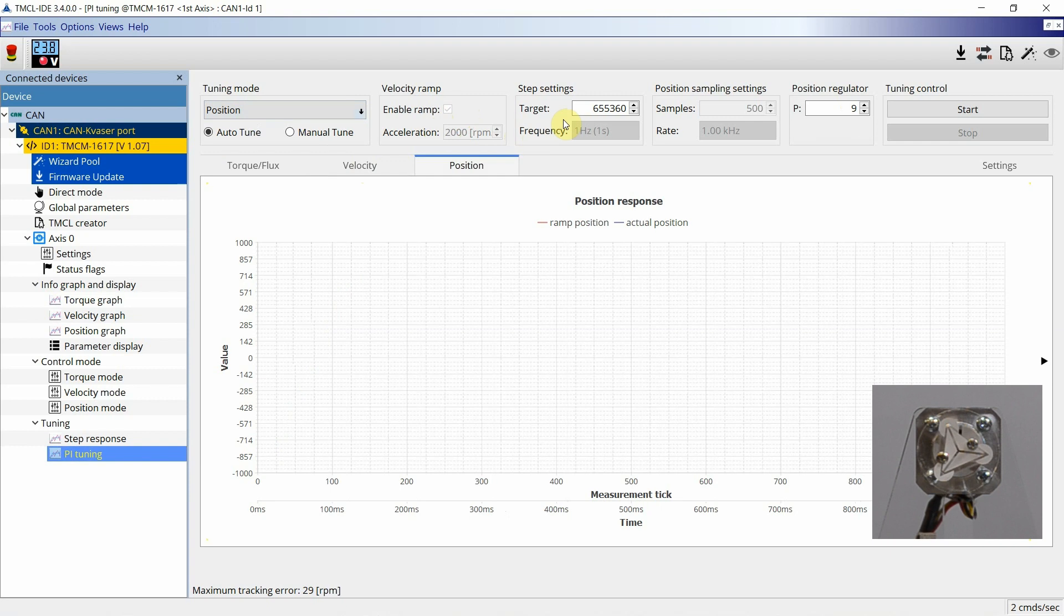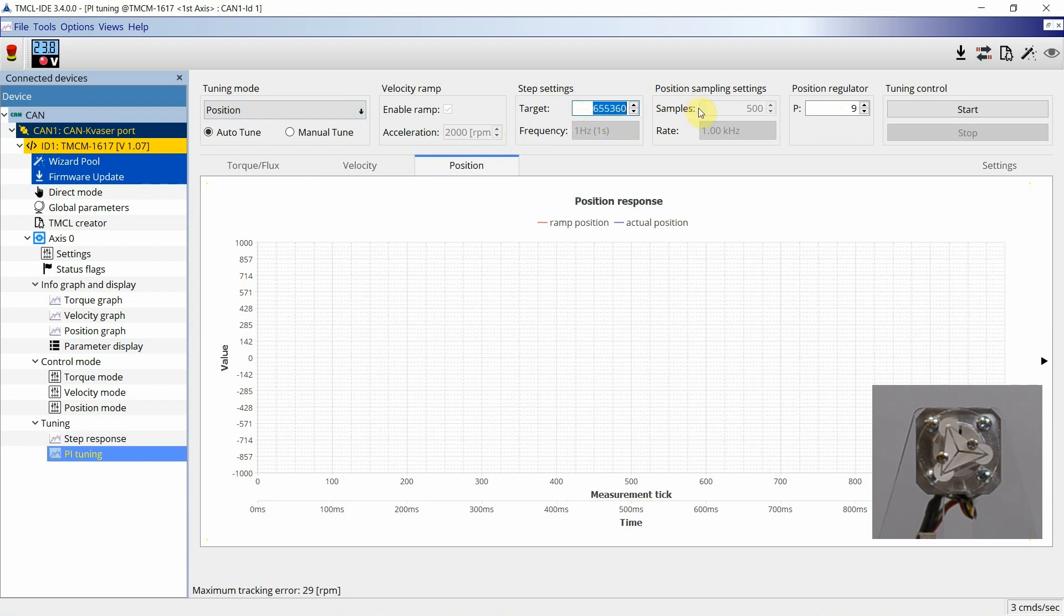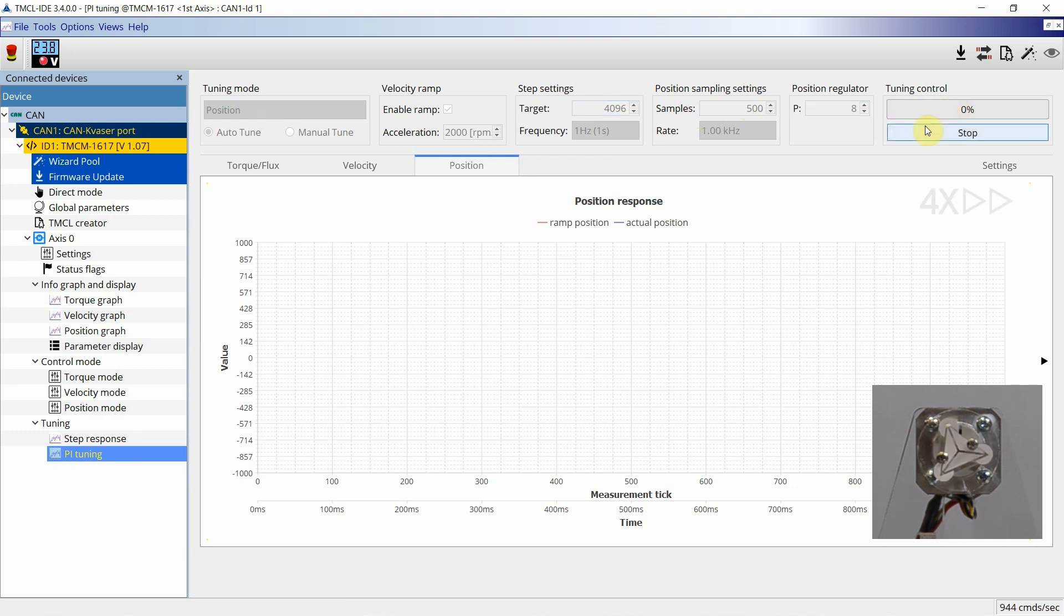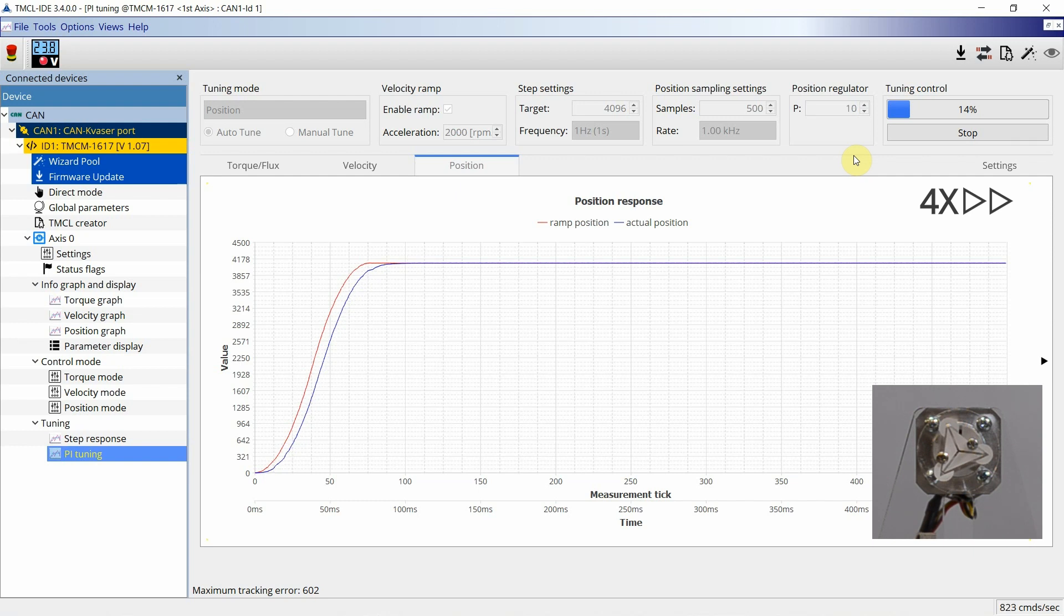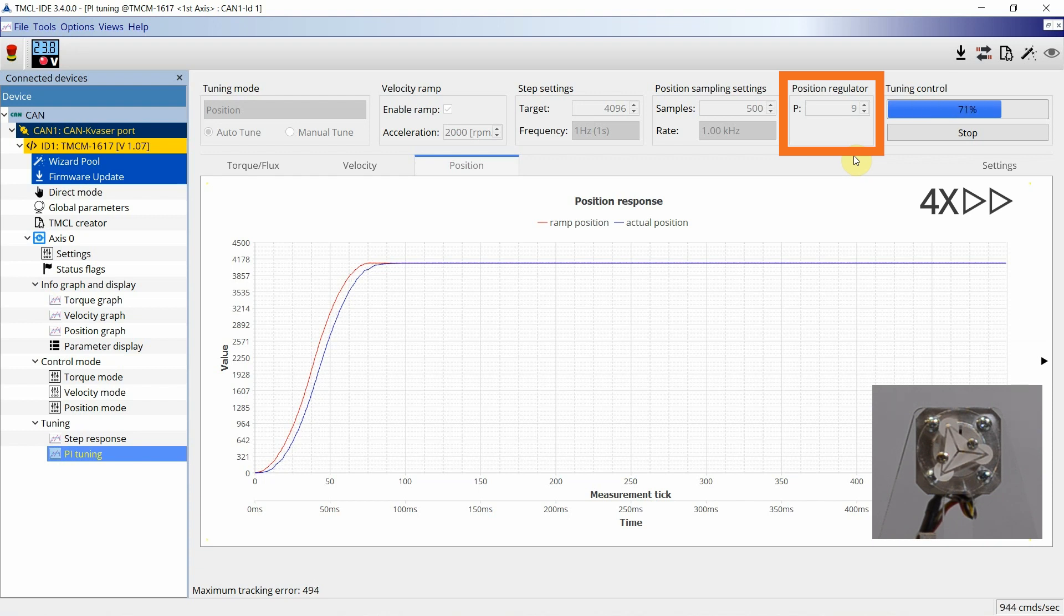In the auto-tuning sequence, the motor will perform target steps as configured here. With a 4096 pulse encoder, a value of 4096 will be equal to one motor revolution. Again, this should be set according to the actual application. Then, start the auto-tuning. The P value will be automatically adjusted until optimal settings have been derived.